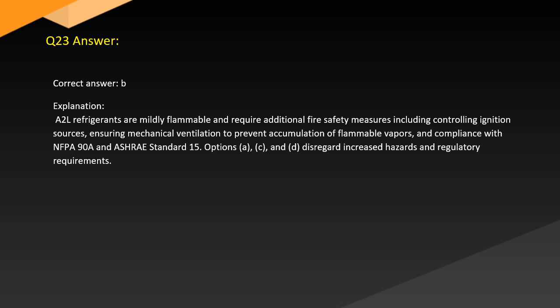Answer. Correct answer: B. Explanation. A3 refrigerants are highly flammable and require additional fire safety measures, including controlling ignition sources, ensuring mechanical ventilation to prevent accumulation of flammable vapors, and compliance with NFPA 90 and ASHRAE Standard 15. Options A, C, and D disregard increased hazards and regulatory requirements.